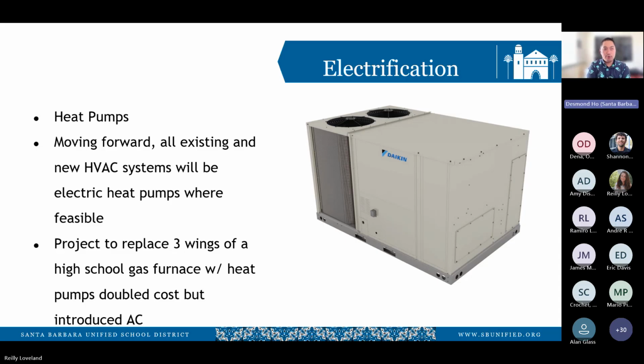One small issue we encountered since switching to heat pumps: a lot of teachers are used to having windows and doors open, and they're having a difficult time shifting to closing them. We found that installing door or window switches that disable the compressor or heating coils after a time delay, if doors or windows are left open, is a very effective way of saving energy and protecting the equipment.